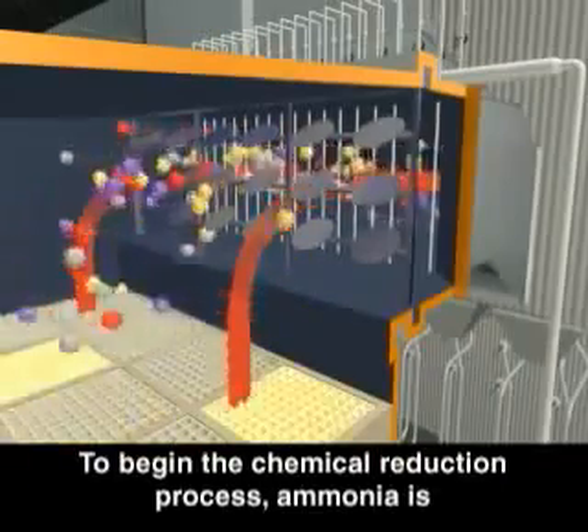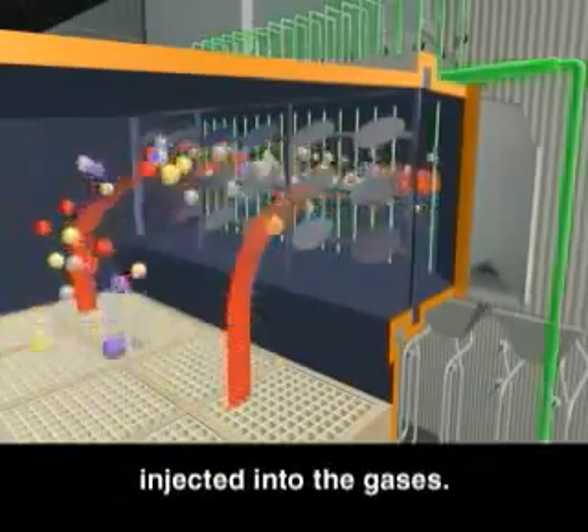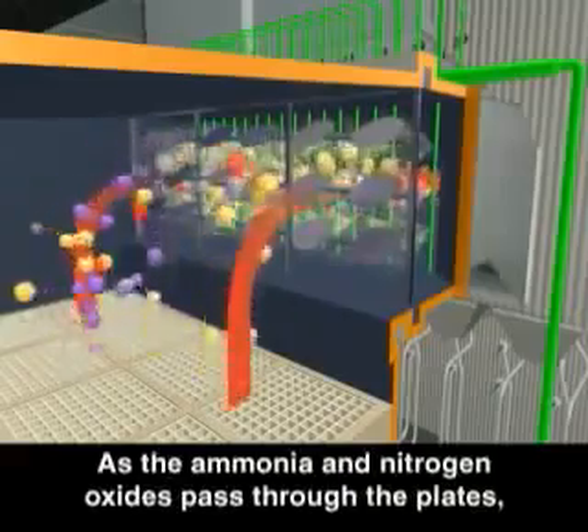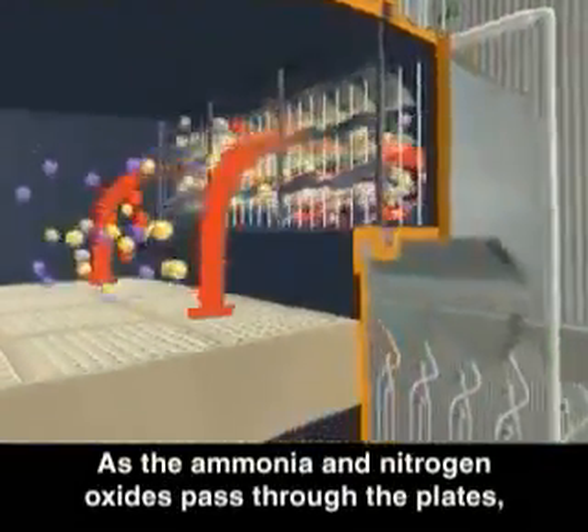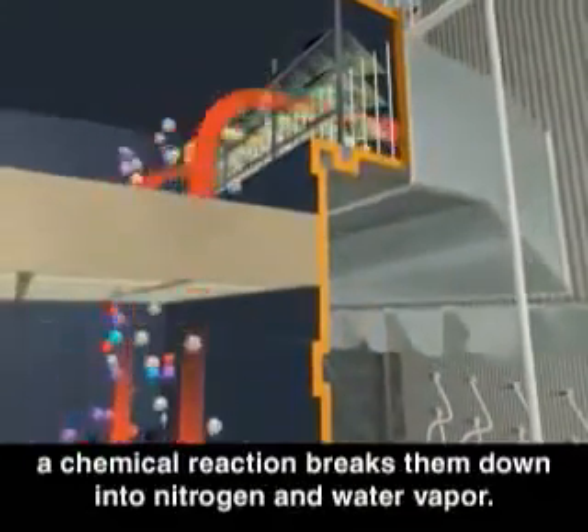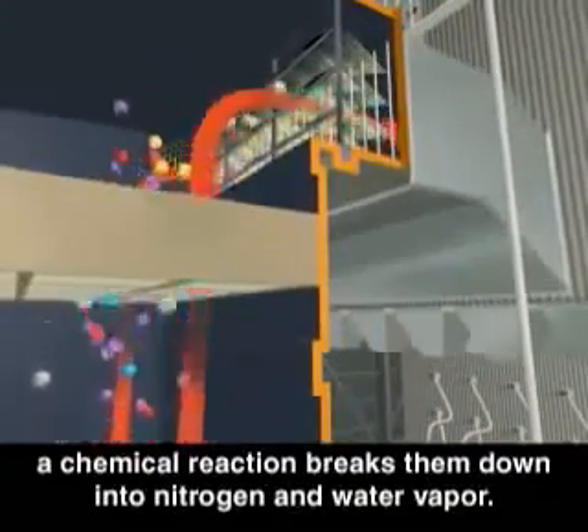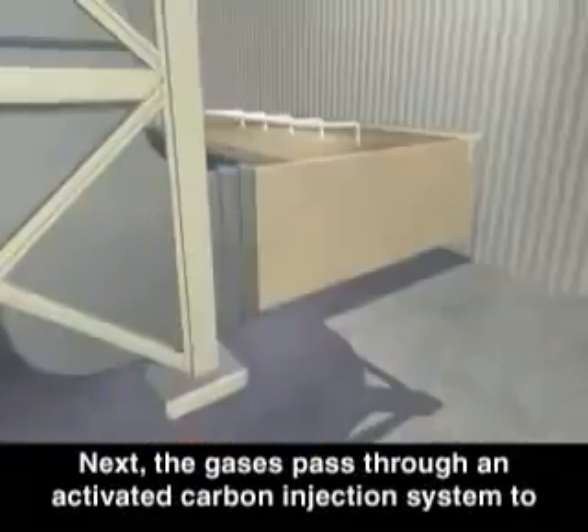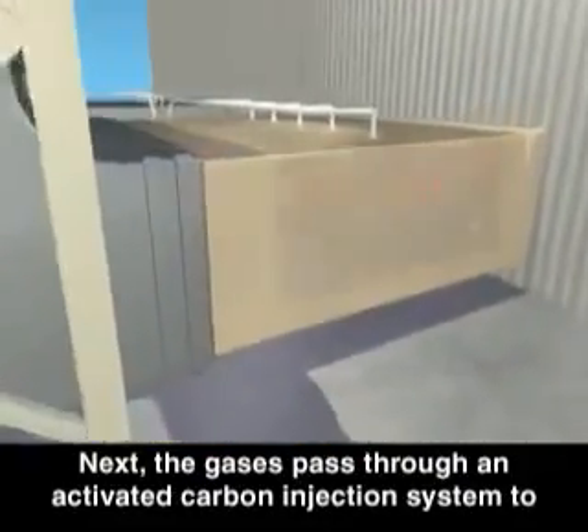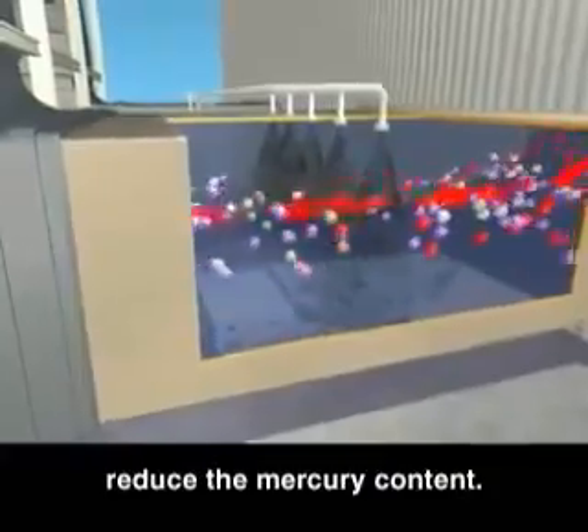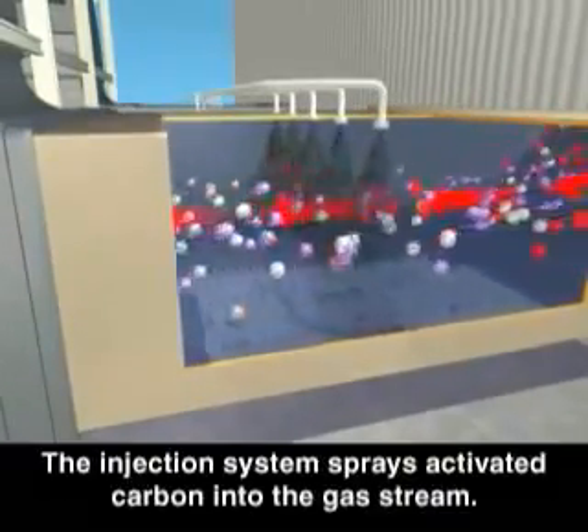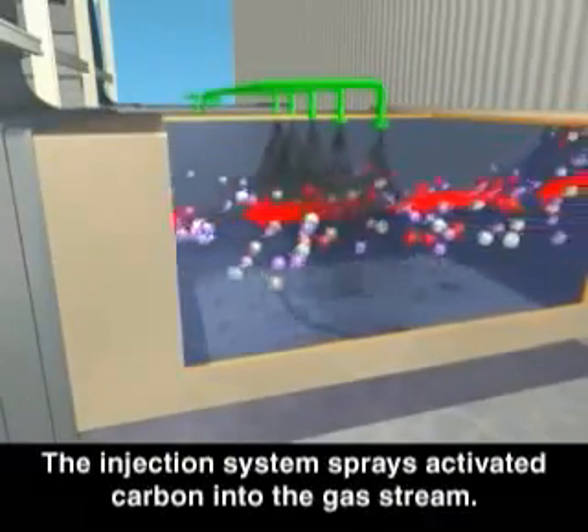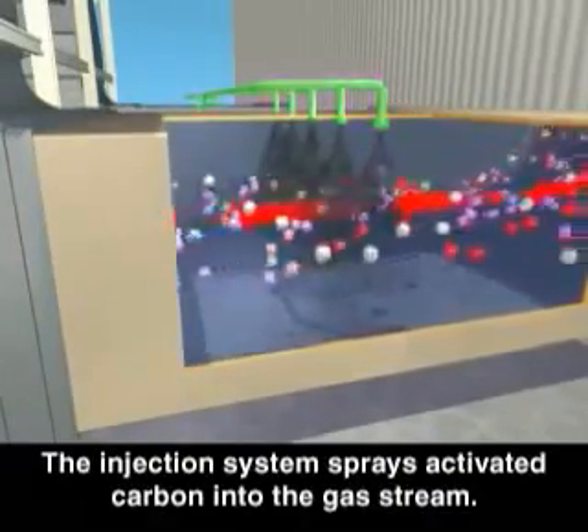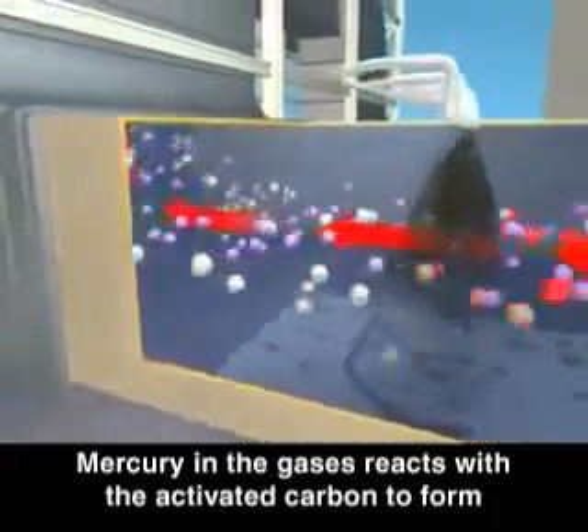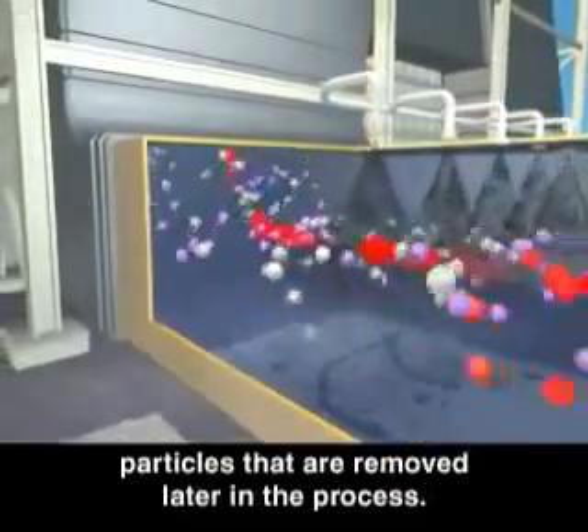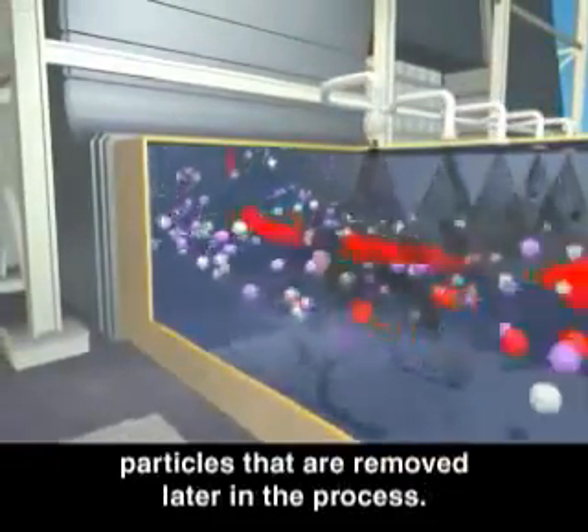To begin the chemical reduction process, ammonia is injected into the gases. As the ammonia and nitrogen oxides pass through the plates, a chemical reaction breaks them down into nitrogen and water vapor. Next, the gases pass through an activated carbon injection system to reduce the mercury content. The injection system sprays activated carbon into the gas stream. Mercury in the gases reacts with the activated carbon to form particles that are removed later in the process.